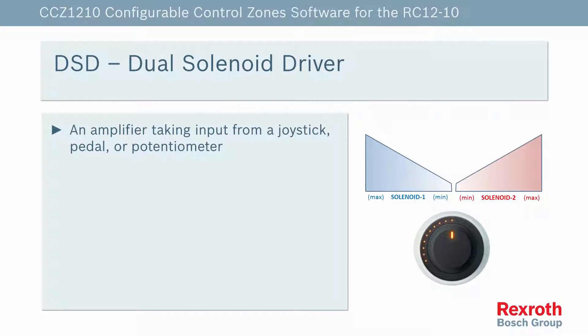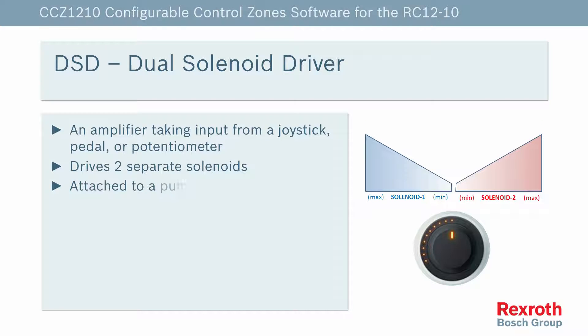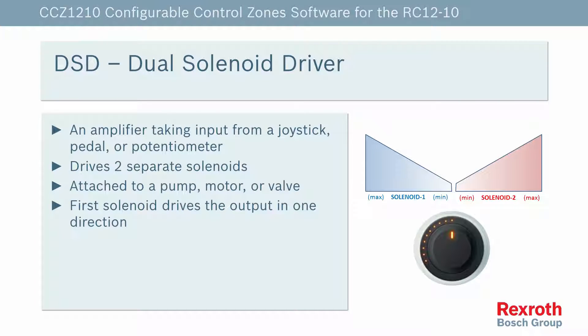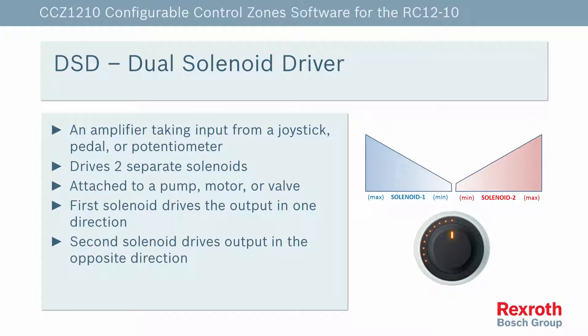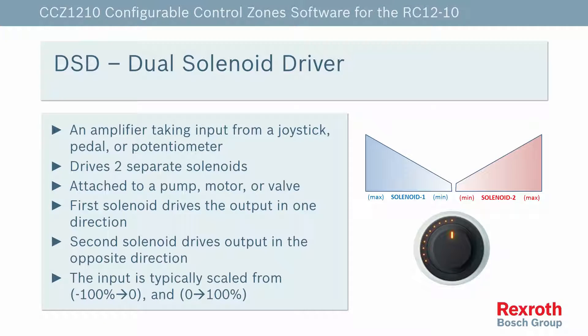The dual solenoid driver is essentially an amplifier that takes input from a joystick, a foot pedal, or some sort of potentiometer, and then drives two separate solenoids. Typically, the solenoids are attached to a pump, a motor, or a valve. The first solenoid drives the output in one direction, and then the second solenoid drives the output in the opposite direction. The input is typically scaled from minus 100 to zero, and then zero to 100%.